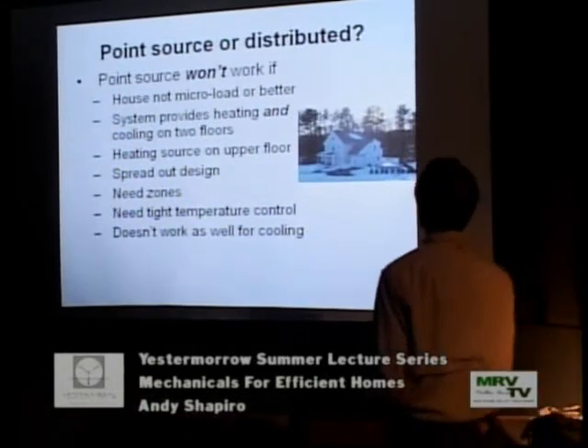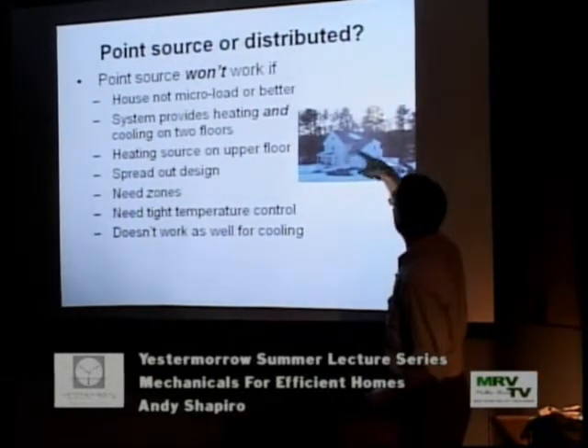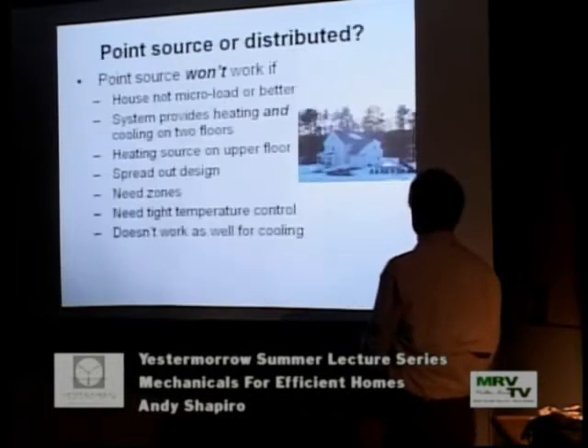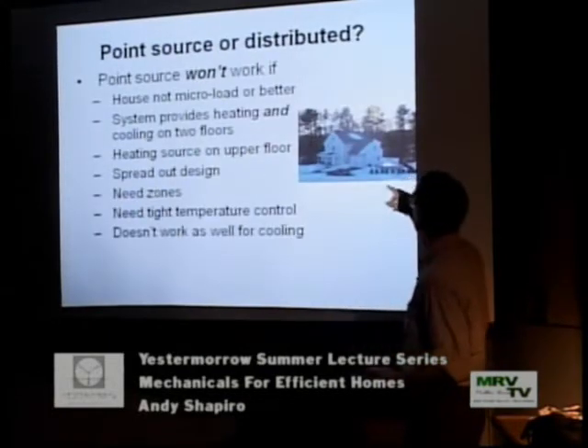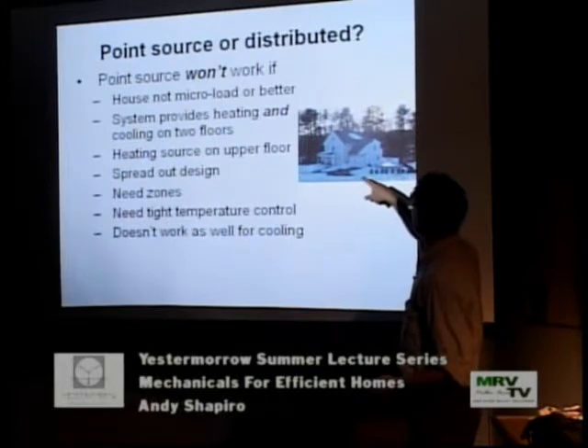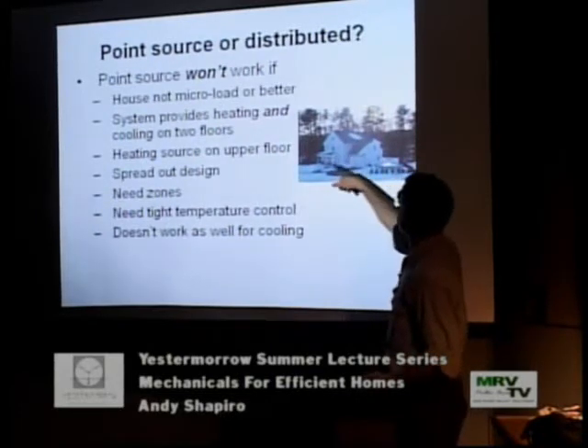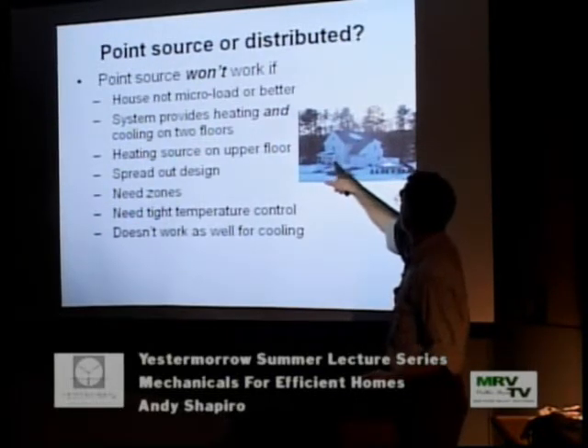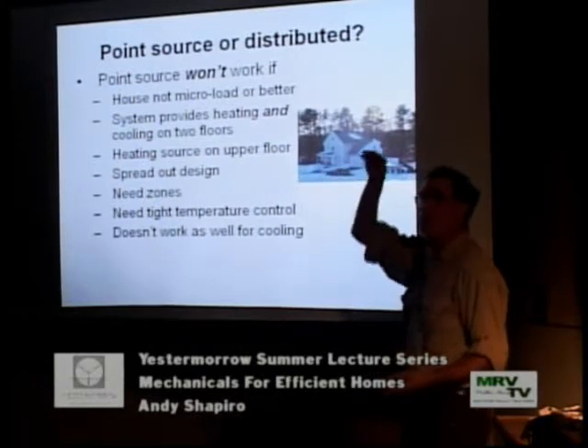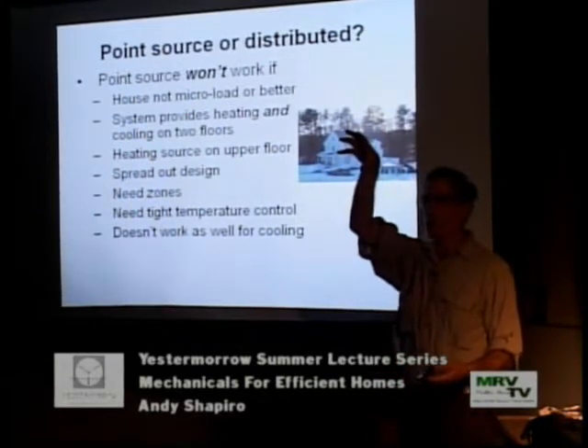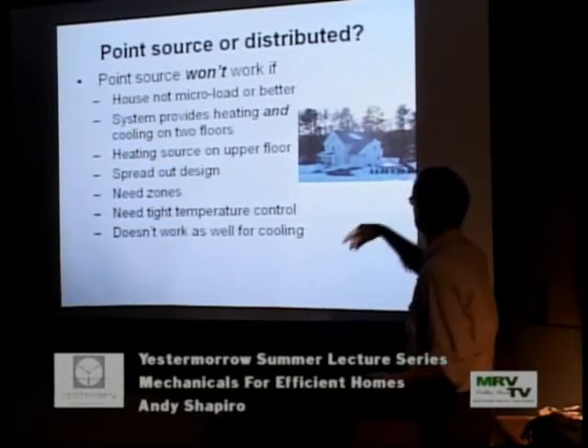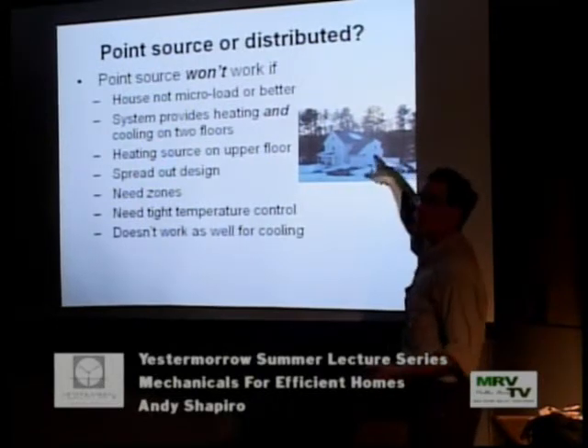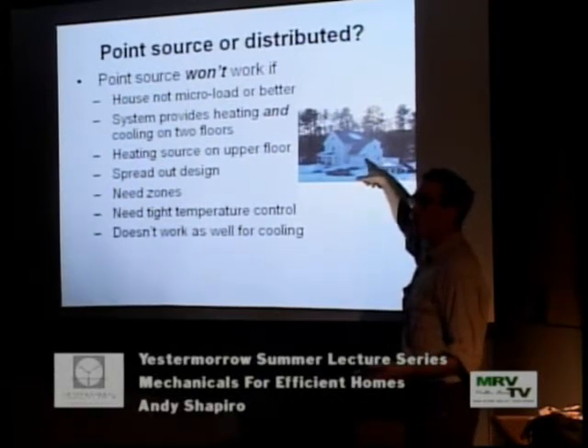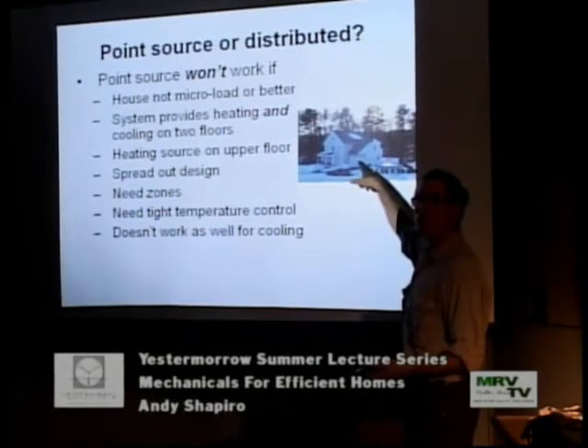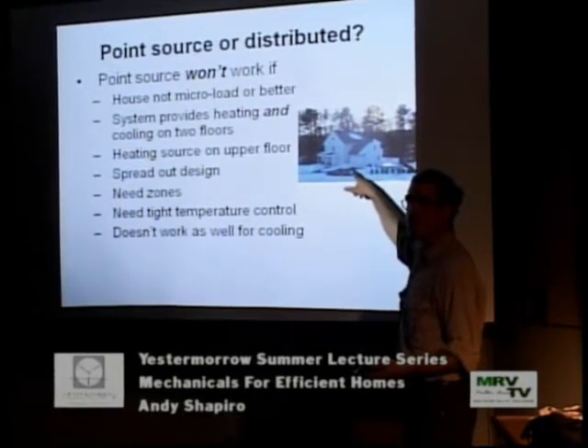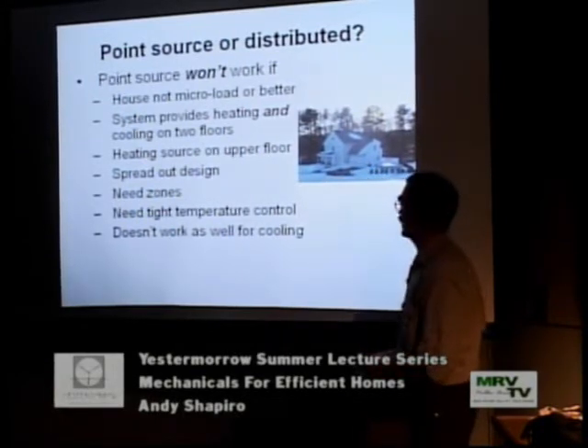Here's a house - a super insulated house. A study on this was done by Building Science Corps, which they talked about recently. This super insulated house has a heat pump for the first floor and one for the second floor - the kind that sits on the wall, a point source unit, not ducted. There's a bedroom over here, and that bedroom is cold. The house is super insulated, but it's just too spread out - it didn't work well enough. It was 10, 12 degrees colder in there than the rest of the house. It was getting to be a little much.